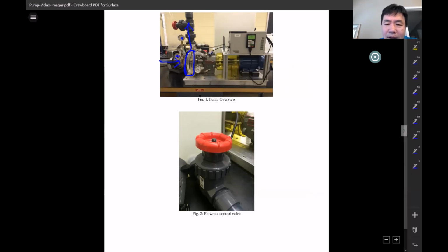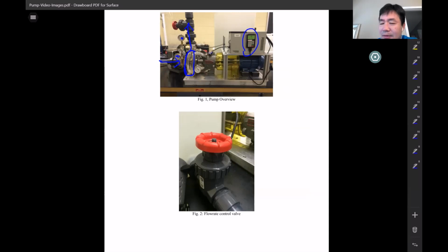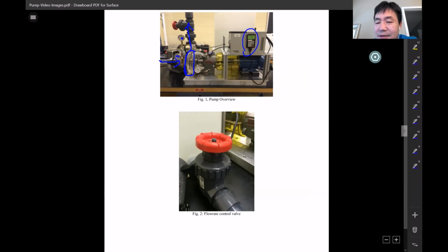So there's a panel here. In this panel is to change RPM. Okay, change RPM. Last time, remember when we did the system curve measurement, we set the valve the same, never touch it. We change this RPM to represent different pumps. Then you can measure the system curve, right? Not measure RPM, set different RPMs.